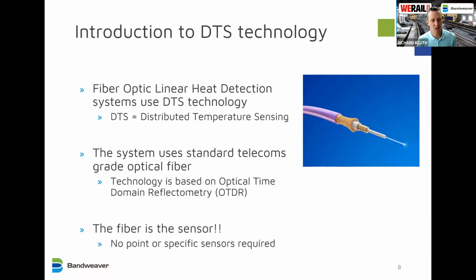So what is the technology behind this fibre optic linear heat detection? It's known as distributed temperature sensing technology, or DTS technology. And really the key to this technology is that the system uses standard telecoms grade optical fibre, so no specialist sensing points are required. This is because it uses a technology called optical time domain reflectometry, which is a bit of a mouthful, so I'll call it OTDR, but it's very similar to the radar time of flight principle. On the next slide, I'll go into a bit more detail. But the key takeaway is the fibre is the sensor. There are no specific points, and you get complete coverage.